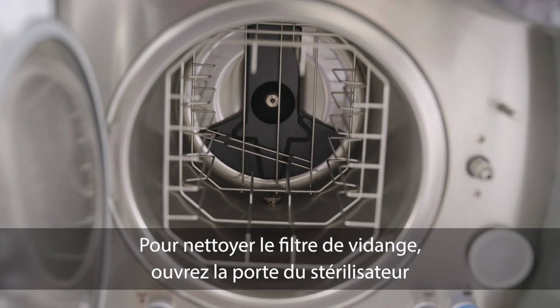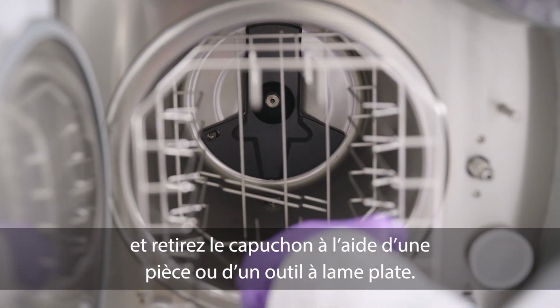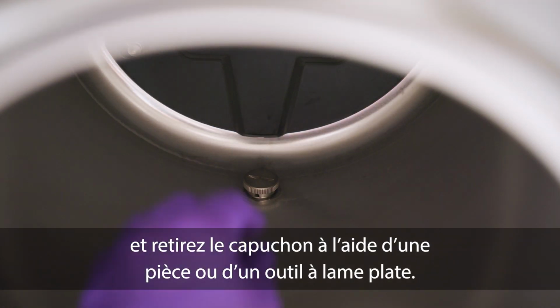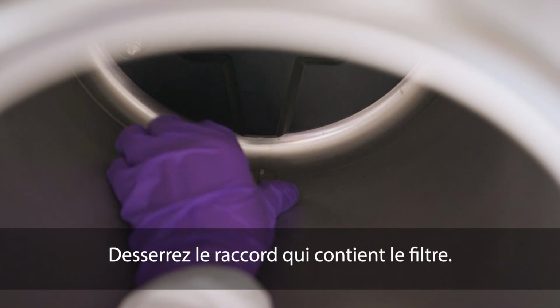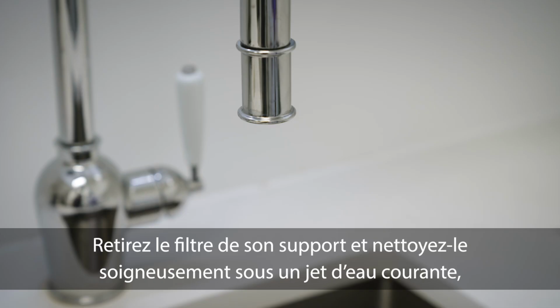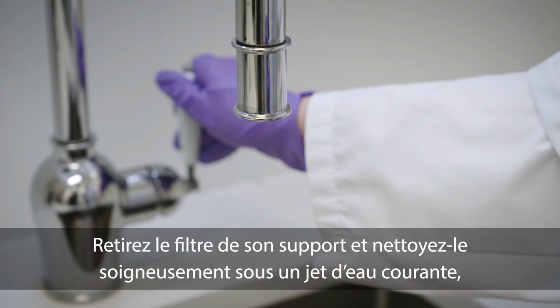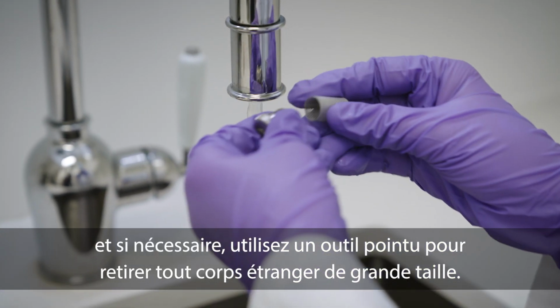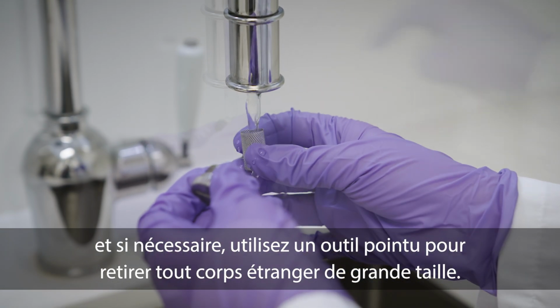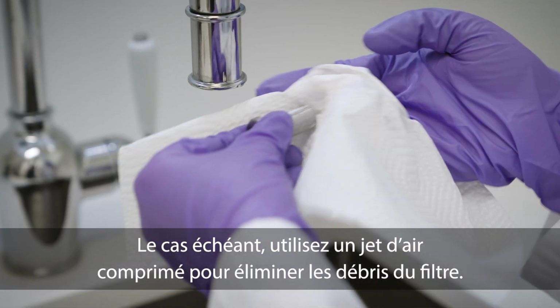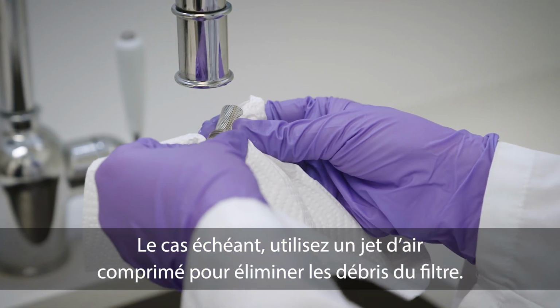To clean the drain filter, open the sterilizer door and remove the cap using a coin or flat-bladed tool. Loosen the union that contains the filter. Remove the filter from its support and thoroughly clean it under a jet of running water, and if necessary, use a sharp tool to remove any large foreign bodies. If available, use a jet of compressed air to remove debris from the filter.